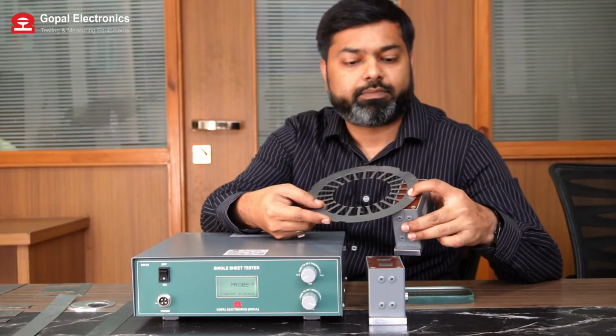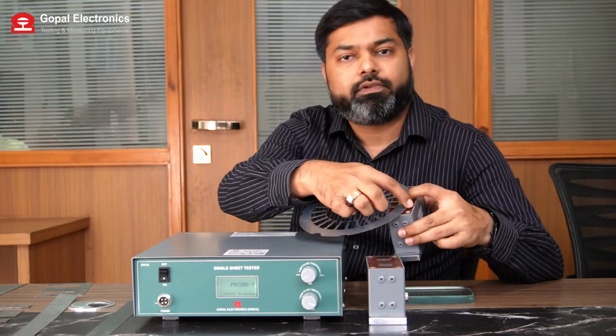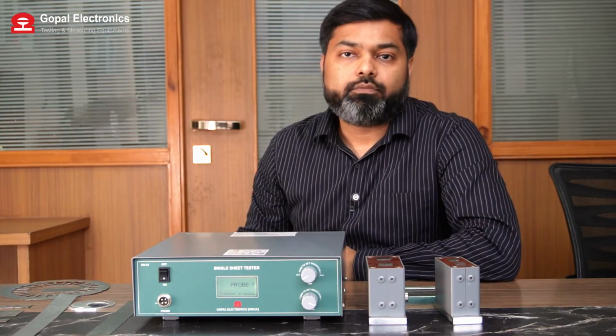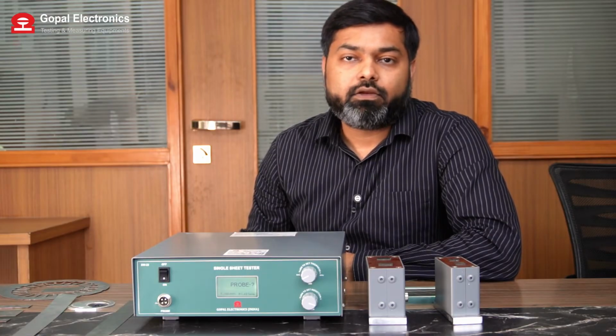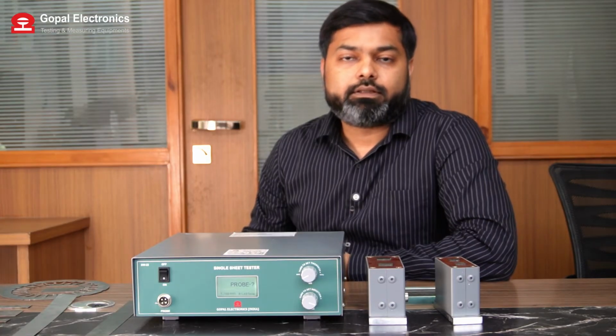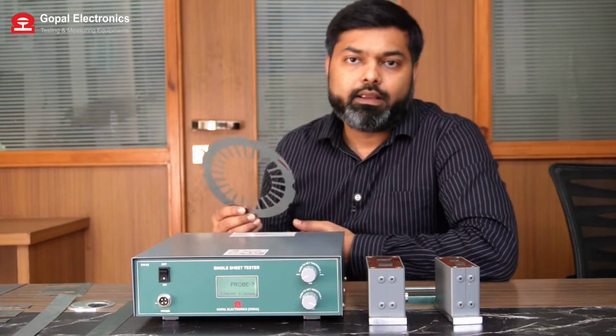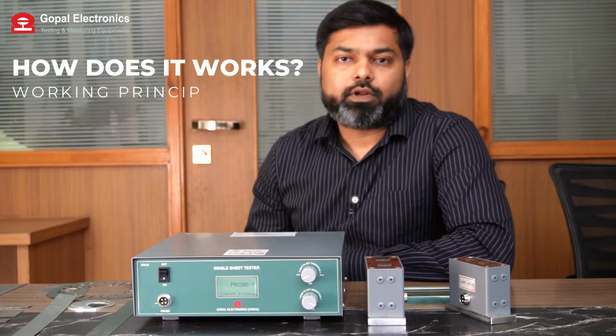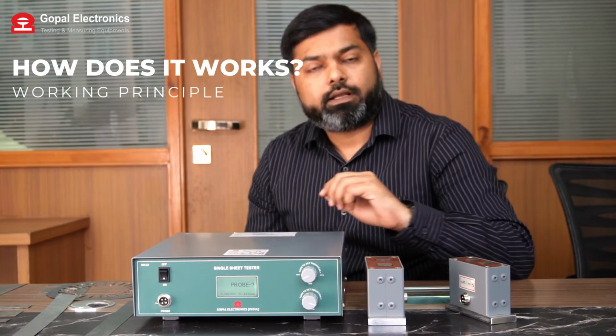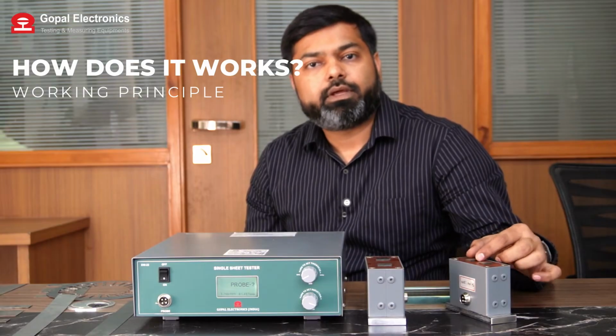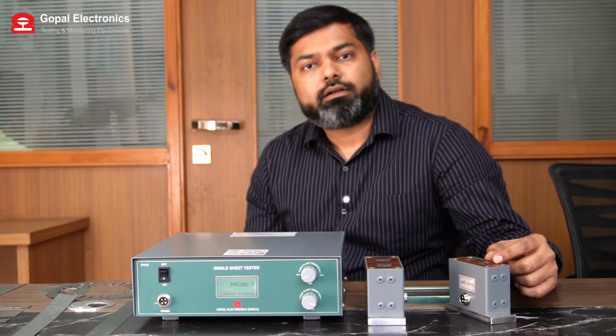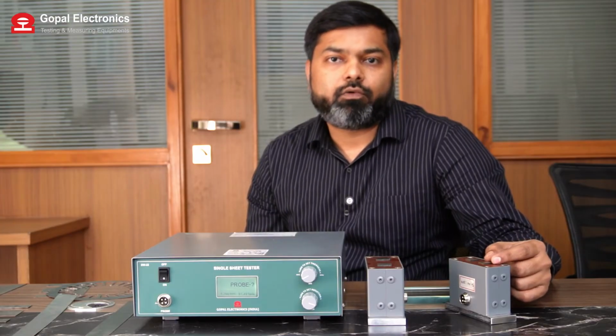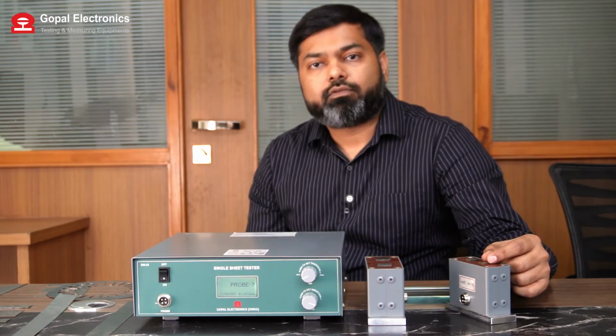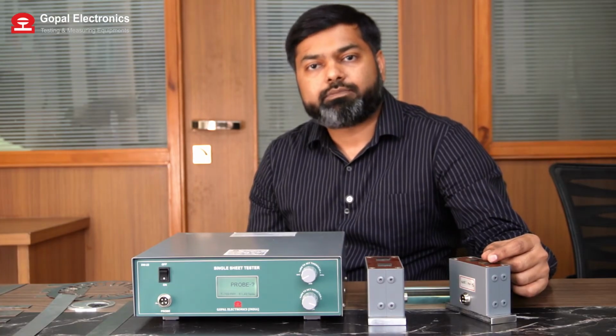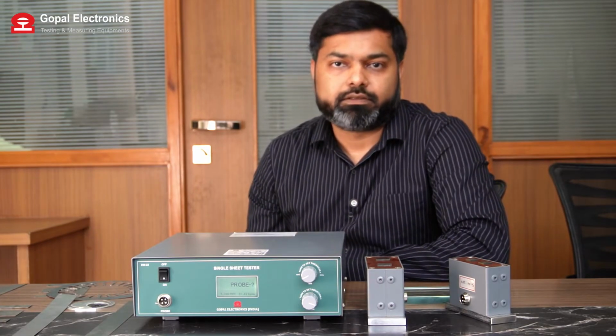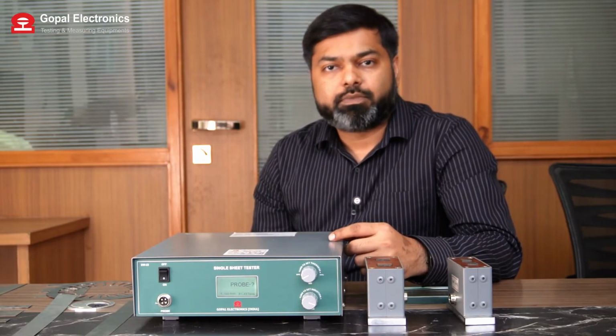That too with the surface test method. You can see, a very small portion we are testing by the surface test method. So you may observe minor variation in a reading while comparing to the final product, because the test depends on the surface of the sample and quality of the sample. Working principle of this equipment is very simple. A single stamping is magnetized using a primary coil of this probe, and feedback power is measured by a 0.1% accurate wattmeter and gives you the calculated result directly in watt per kg as per the thickness and induction you have set in the machine. Now let me count you the features of this machine.